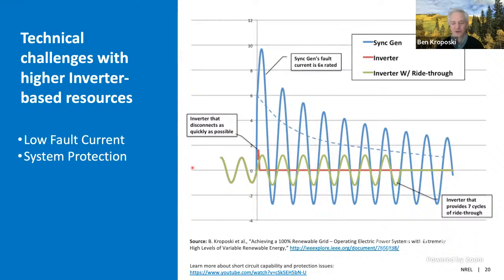But if we think about a fault happening from a normal synchronous generator-based grid, when a fault happens, a lot of the fault current is delivered from synchronous generators. You can see here if the normal load condition was serving something like this, a fault happens here at time 0, you get this really big spike in output current from synchronous generators.